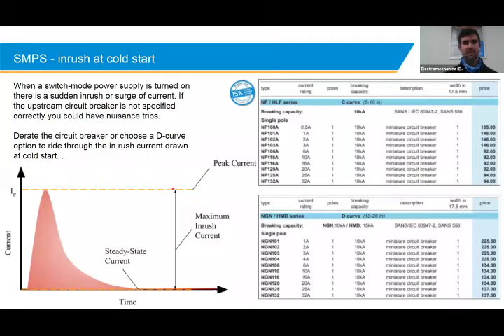All right. Just a note on the switch mode power supplies. Something I remember picking up as an apprentice many years ago is the switch mode power supply's inrush current. Typical at a cold start, really. So what I mean by a cold start is when the power supply has been off for, say, a number of hours and its capacitors are completely drained. When you turn on that switch mode power supply after a lengthy off period, you would have a sudden inrush. And the inrush current is many more times than, say, 10 or 20 times the rated nominal input current of that power supply. So it's something to consider and to remember. You can have nuisance trips if you try and match your upstream circuit breaker too close to that nominal input current of the power supply.